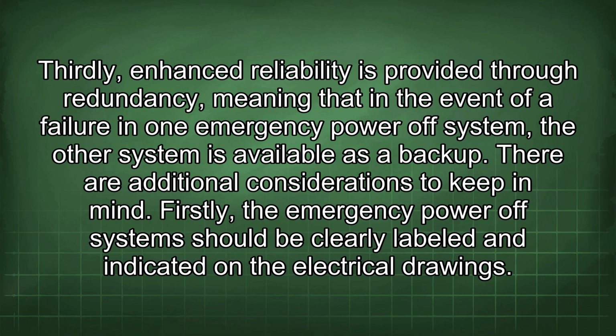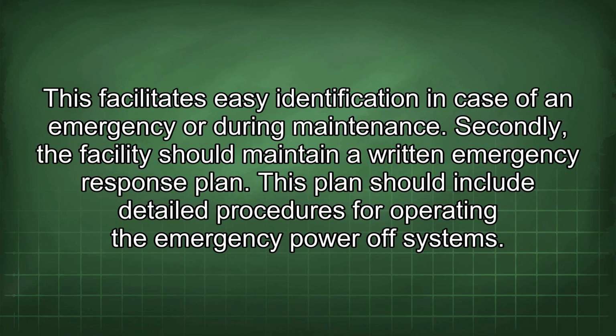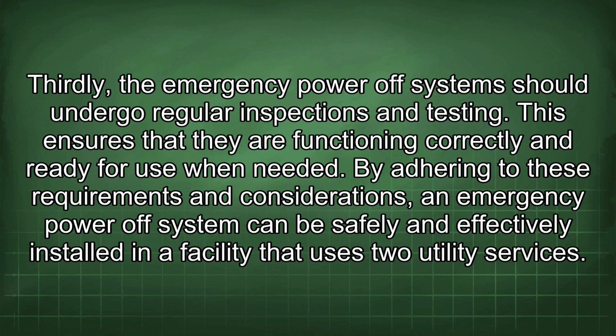There are additional considerations to keep in mind. Firstly, the emergency power-off system should be clearly labeled and indicated on the electrical drawings. This facilitates easy identification in case of an emergency or during maintenance. Secondly, the facility should maintain a written emergency response plan. This plan should include detailed procedures for operating the emergency power-off systems. Thirdly, the emergency power-off systems should undergo regular inspections and testing. This ensures that they are functioning correctly and ready for use when needed.